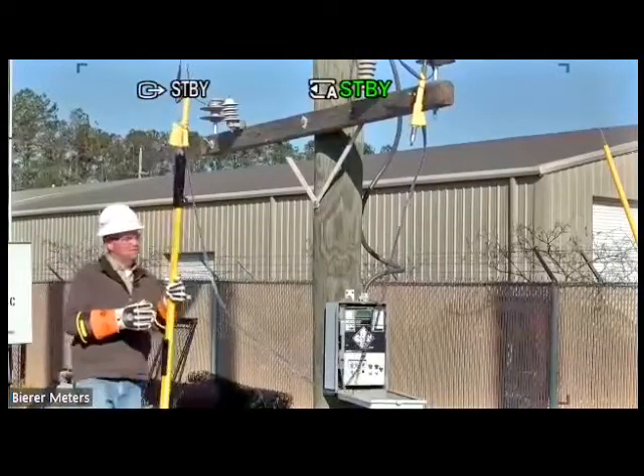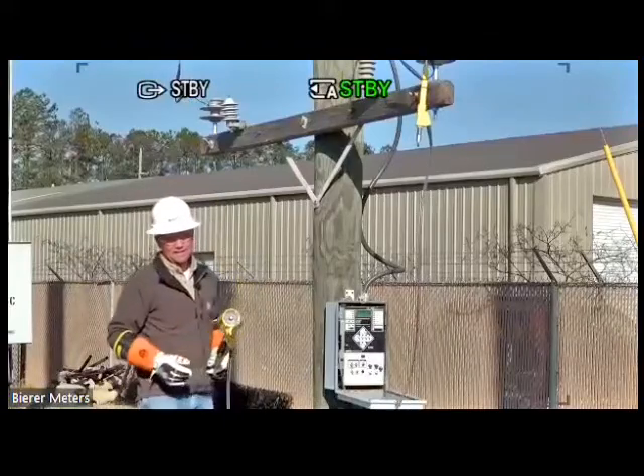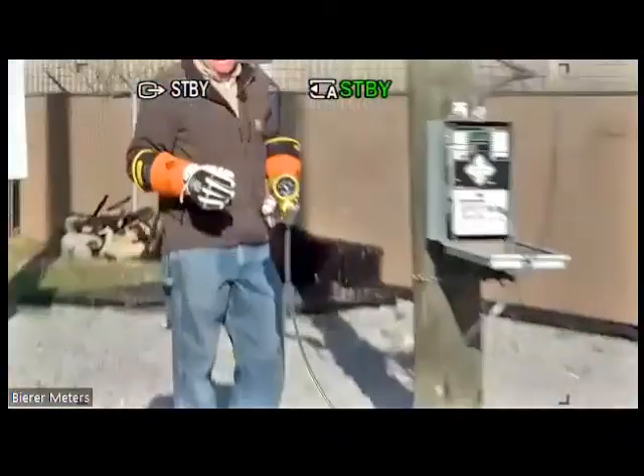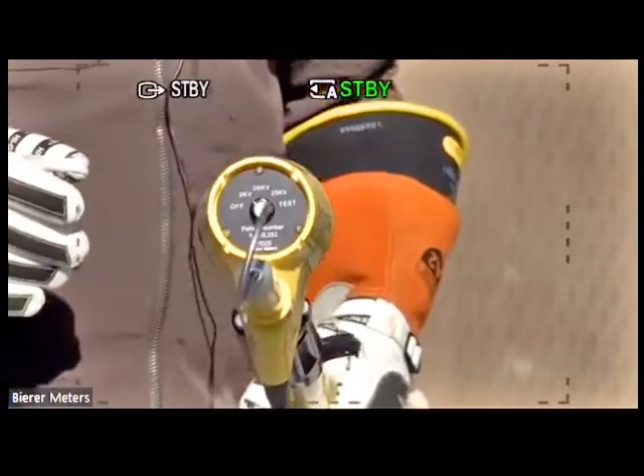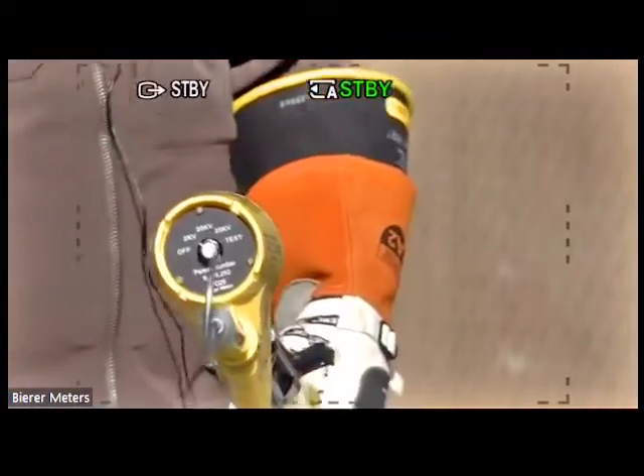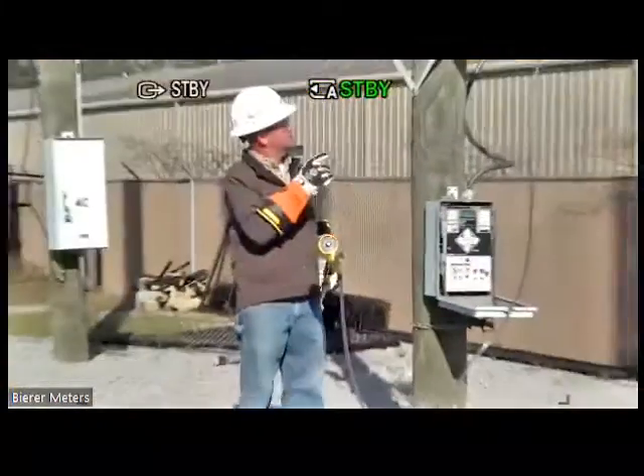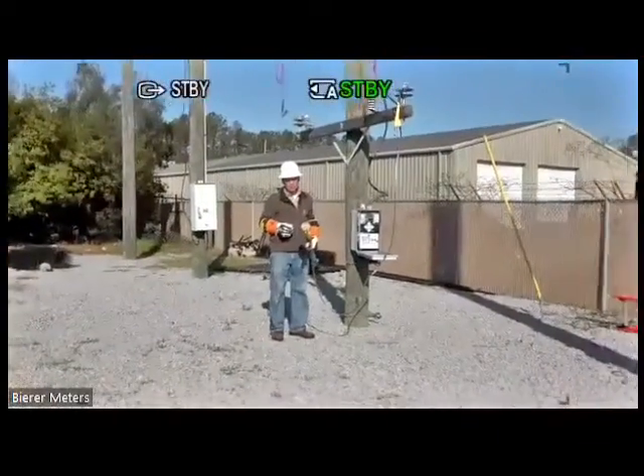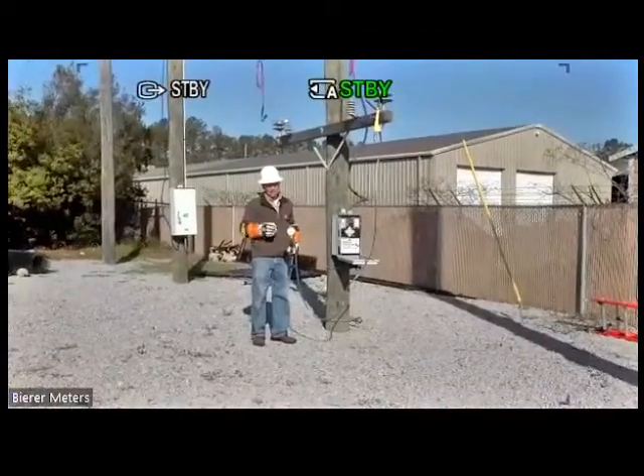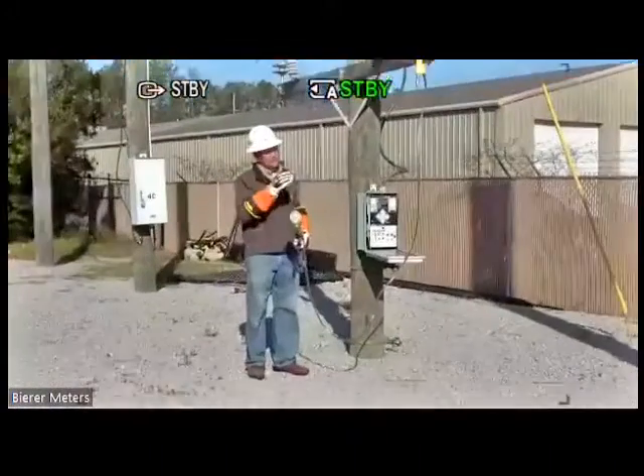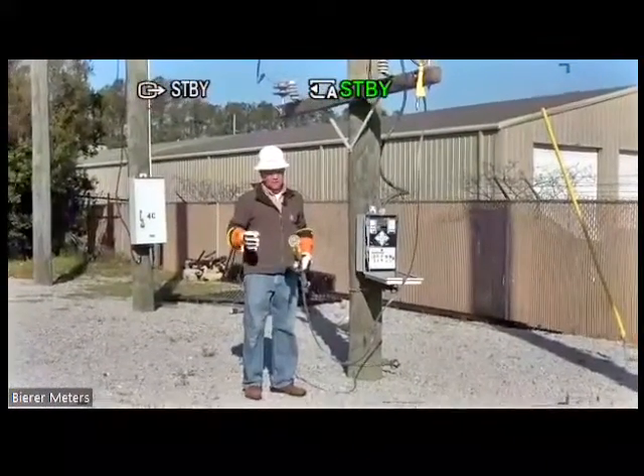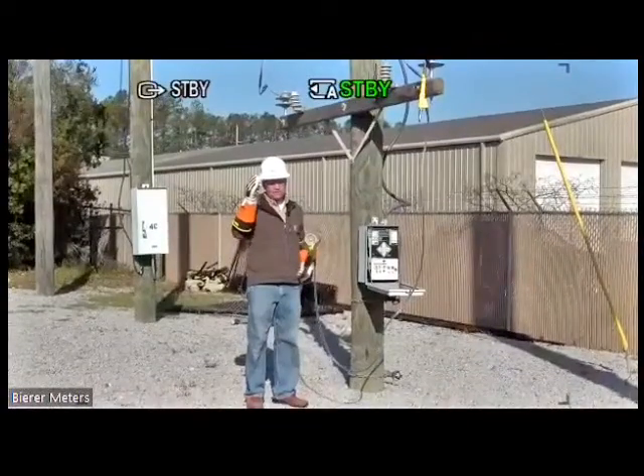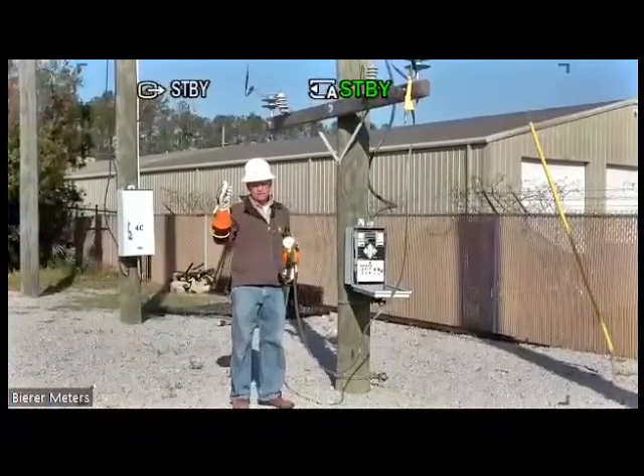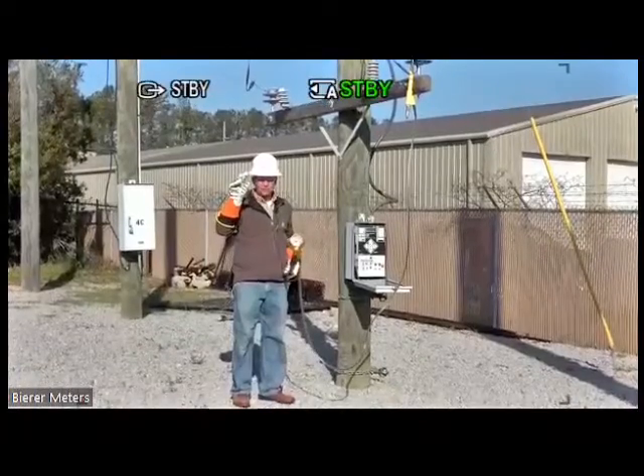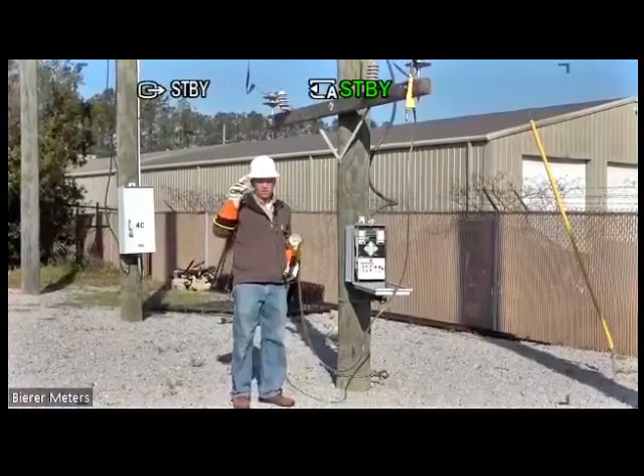So I want to put this tool in the 2 kV switch position. Ryan, zoom in on that. I want to put this tool in the 2 kV switch position for the best accuracy. And again, this is replacing a single use item. And we have this rigged up a little bit differently than what you would normally see in the field. We're in the process of still modifying our training yard. Normally this regulator would be down fairly low, like in a substation where you would just have the line side bushing, the load side bushing. You can go to line or load, or you can go line to ground or load to ground.